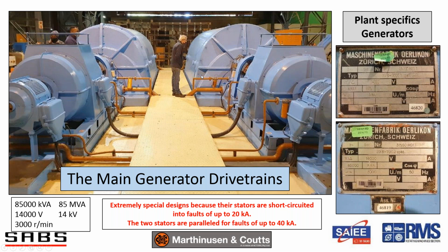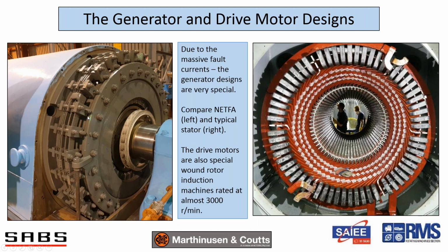Okay, to illustrate how special these stators are, on the right you can see a winding that we just recently completed of a 36 megawatt 2-pole. You can see your Roebel bars, your transposed bars coming out here. You have top and bottom bars, connected in these blocks here and covered with these clip caps. Then the support around the end is a support ring that holds the winding in place, and you can see roping here, three layers of roping.